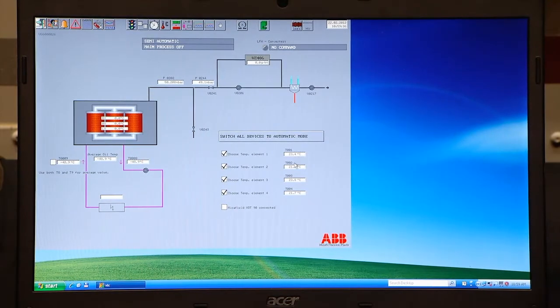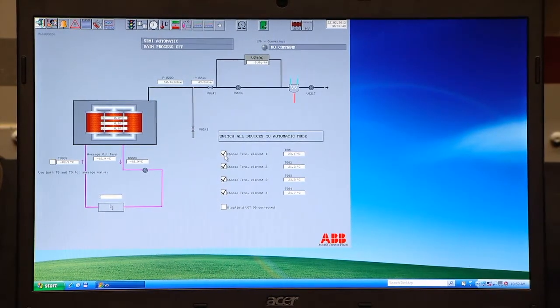4 temperature sensors are installed inside the transformer. You select the sensors that you have installed, and this selection is for alarm purposes. If you have a break on the cable, you will then have an alarm if you have checked the checkbox. If you uncheck the checkbox, that means that only these 3 sensors are controlled. Now this alarm is only for checking if the sensor is broken or not broken.